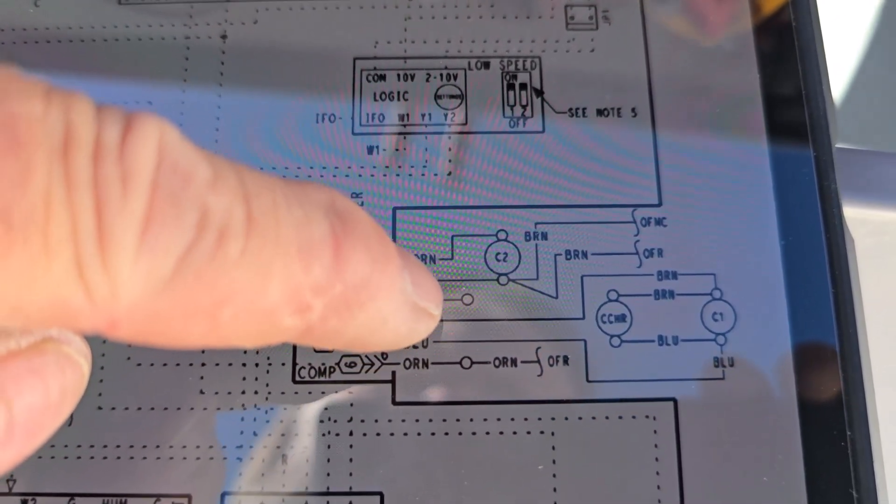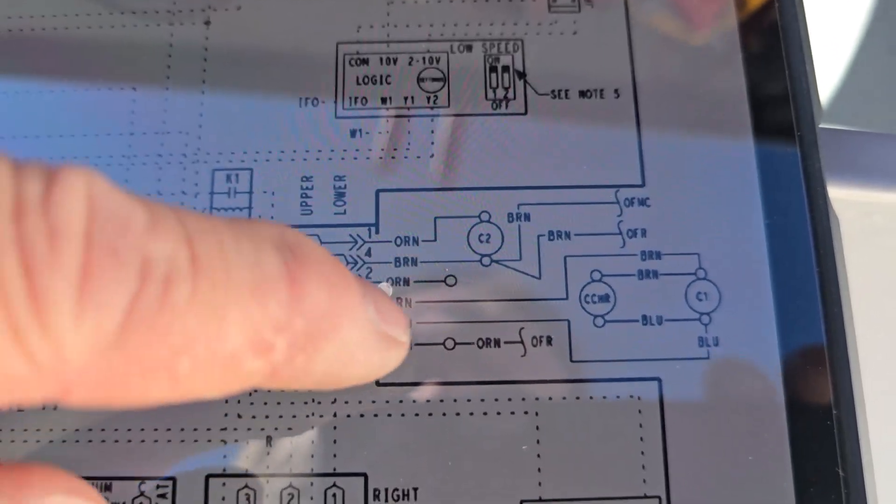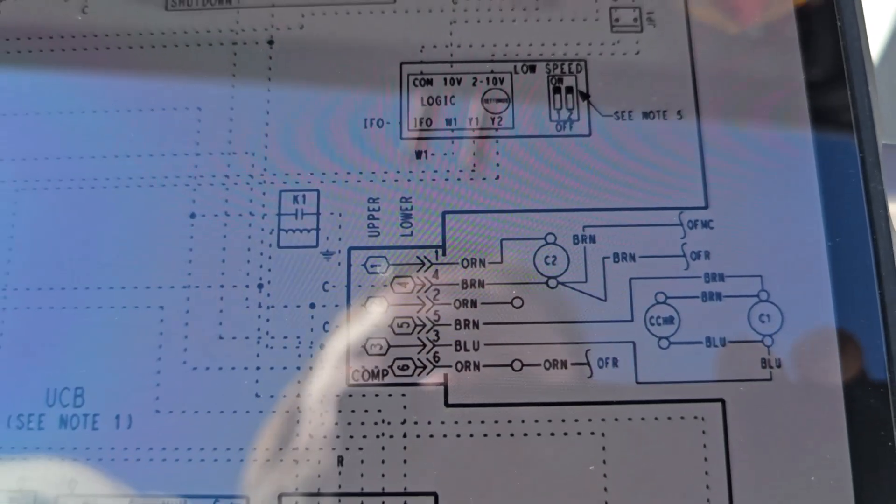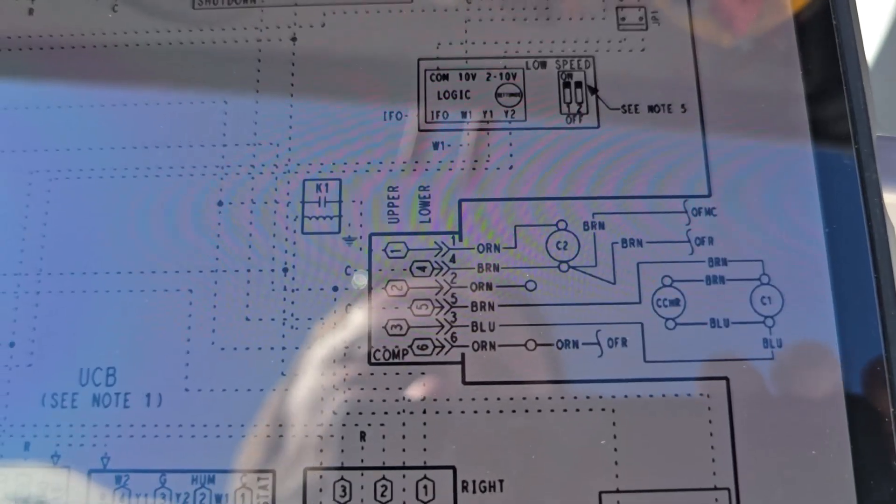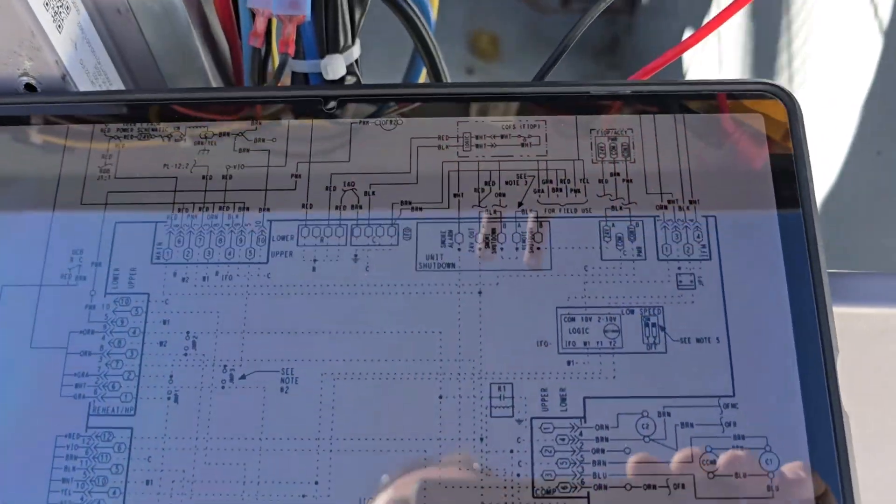But this wire should be not hooked up to anything. That's a female connector, just shouldn't be left open. But with a jumper over here onto the, it landed on here, it always tests 24 volts with Y1. So it's just putting it right to C2, just jumpered them together. For an interesting find, for an interesting little booby trap.